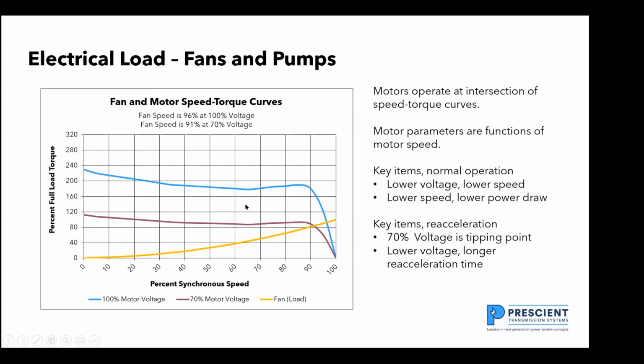And so what I did is I put down a speed torque curve for a typical fan and a typical motor. If you look at the fan characteristic here in orange, as the fan speed changes, the torque requirements change. But the motor characteristic is a function of the terminal voltage on the motor. If I have 100% terminal voltage on the motor, the blue line is how much torque the motor can produce. And the intersection of the fan curve and the motor curve is the operating speed of the motor.